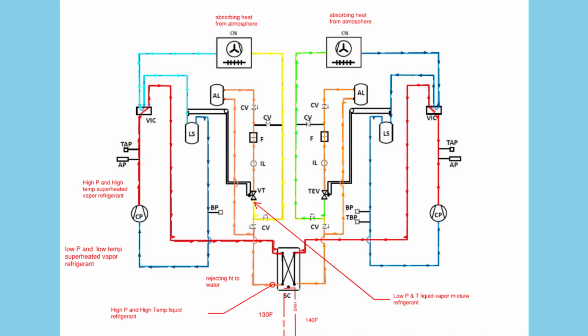2. Heat release, condenser, water heat exchanger. The high-pressure vapor passes through the four-way reversing valve and enters the heat exchanger, which now acts as the condenser. Here, water circulates through tubes on the opposite side. The refrigerant rejects its heat to the water, raising the water temperature. As the refrigerant gives up its heat, it condenses into a high-pressure and high-temperature liquid. The water leaves the heat exchanger warmer. This is the domestic hot water or heating hot water supplied to the building. The liquid refrigerant next flows through the liquid accumulator, filter dryer, and sight glass. The filter dryer removes moisture and contaminants. The sight glass allows visual inspection to check for bubbles, dirt, or incomplete liquid state.